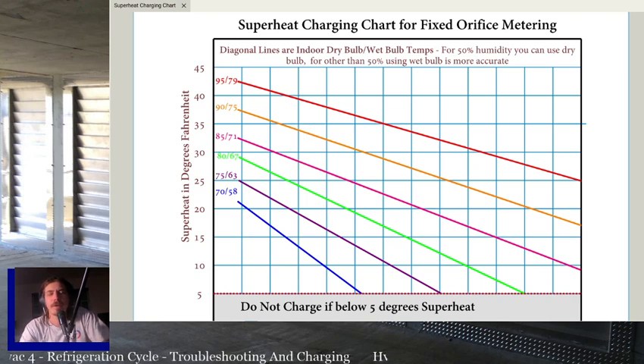If after we go through this stuff down the road, you're trying to troubleshoot an issue and you just can't seem to figure it out, then make sure the charge is good. How do you make sure the charge is good? Just pull the charge out into a recovery cylinder, and if you don't think there are any non-condensables in it, just weigh it back in. If you suspect non-condensables, then you should test for them, and then obviously start with a fresh charge. But if you absolutely cannot figure out what's going on, then just tell the customer, if you have to, I've got to clean the coils and I've got to weigh this charge in so I can figure this out.